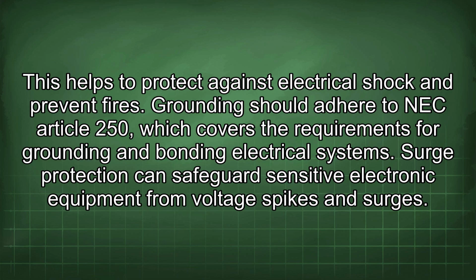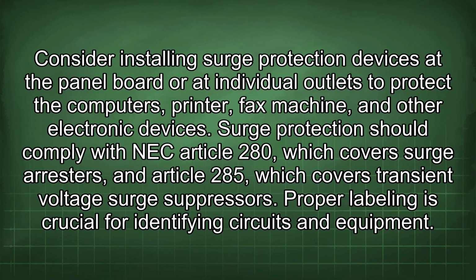Grounding should adhere to NEC Article 250, which covers the requirements for grounding and bonding electrical systems. Surge protection can safeguard sensitive electronic equipment from voltage spikes and surges. Consider installing surge protection devices at the panel board or at individual outlets to protect the computers, printer, fax machine, and other electronic devices. Surge protection should comply with NEC Article 280, which covers surge arresters, and Article 285, which covers transient voltage surge suppressors.